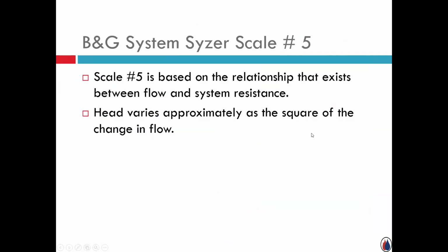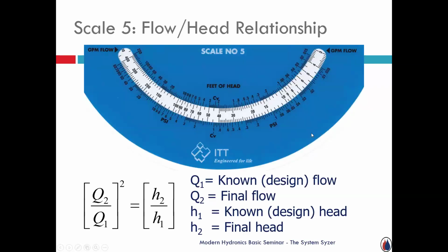Scale 5 is what we're going to focus on a lot tonight, because that has to do with, as we get into system curves again, and we get into pump affinity laws and how that all plays out. Scale 5 is that relationship that exists between the change in flow and the change in head, and that corresponding difference. So the head is kind of a basic statement. The head varies approximately as the square of the change in flow. And we'll go through a couple of examples here.